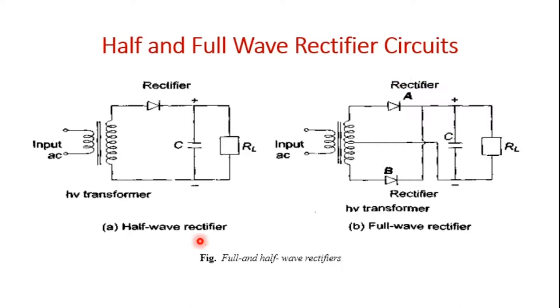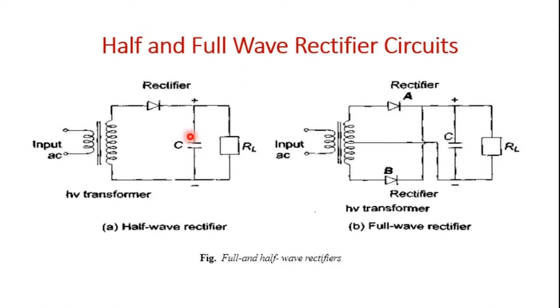In the half-wave rectifier, the capacitor is charged to V-maximum from the AC voltage of the secondary of the high voltage transformer during the conducting half cycle. In the other half cycle, the capacitor discharges into the load. The value of the capacitor is chosen such that the product of capacitance and R-L is at least 10 times the period of the AC input voltage. The rectifier valve must have a peak inverse voltage of 2V-maximum, and an additional resistance is added in series with the secondary of the transformer.